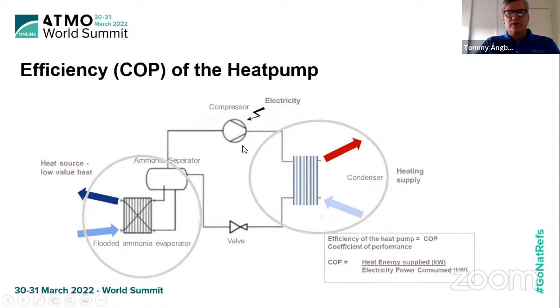And how do we calculate the efficiency? It's the COP. If we are only talking about the heating part, the COP is the heat energy supplied on the heating side, divided by the electric power that we are consuming in the compressors. So if we can increase this ratio, either by reducing the electric power or getting more heating out of the machine, of the heating supply, we can increase the performance. So we're going to look at the two positions: the low side where we have the heat source, and the hot side where we have the heating supply, and where our heat exchangers are incorporated.